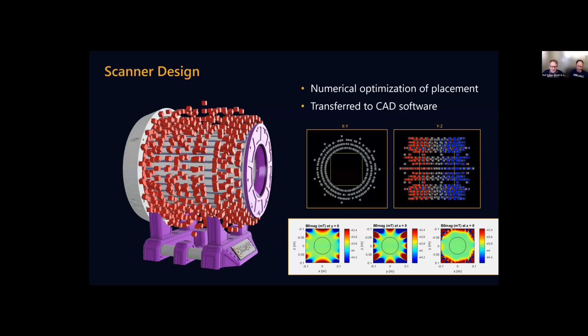Now, under the magnet are different inserts. So the first insert is, or these inserts are stacked into each other. And the first insert is a cooling system for the gradient coils, because it can happen that these gradient coils heat up. And therefore, we have this liquid-based cooling system, which is connected to an external heat exchanger, basically something that you normally use for cooling a gaming PC. And the idea here is to avoid that the magnet heats up, which might result in a drift of the magnetic field. Whether that's really necessary, we don't know yet, but we put it in there.